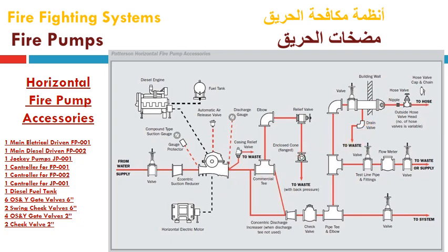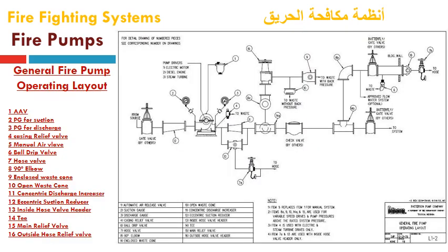So this slide is helpful to get all the horizontal pump accessories recommended by NFPA, and the fire pump manufacturer of this slide is Patterson. This slide is also by Patterson, the same system components, but shown in a different configuration and different line diagram presentation, though we can find the same components similar to the previous slide. It discusses all the accessories required by the pump manufacturer for horizontal pump configuration, especially for fire pumps used in fire pumping systems.